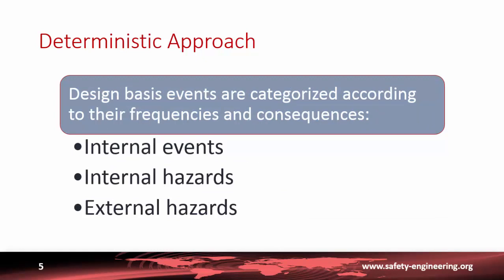The design basis events are categorized according to their frequency and consequences. We make a distinction between internal events — failures of the system itself, components, or plant internal hazards such as internal flooding, internal fire, or load drops — and external hazards, which are events that could occur outside but may affect the plant, such as earthquake, flooding, external fire, or a plane crash. We will see a little bit later how these hazards are treated.